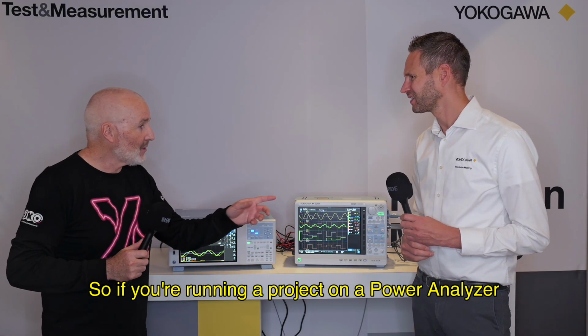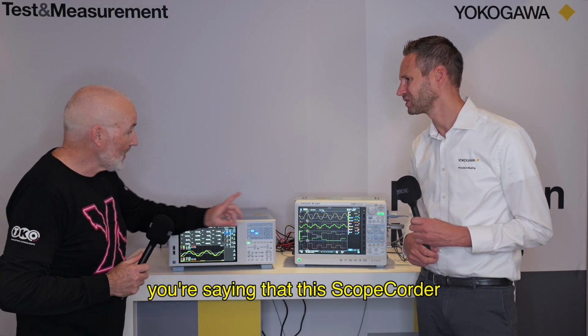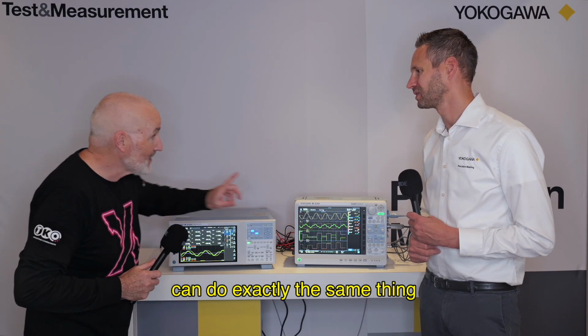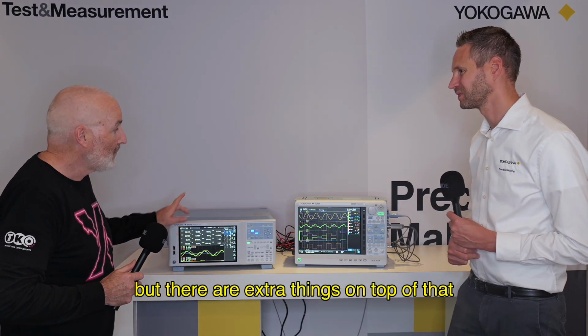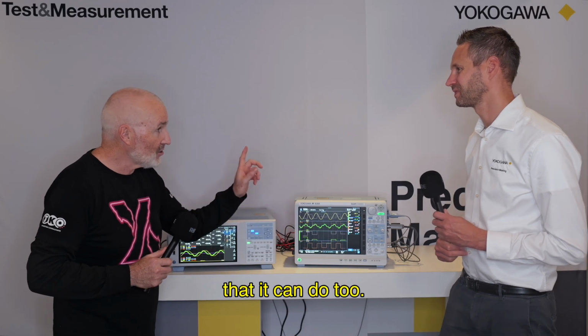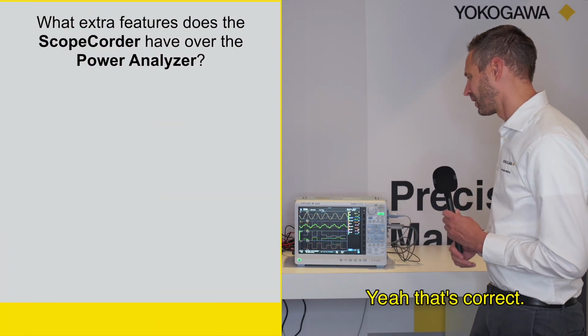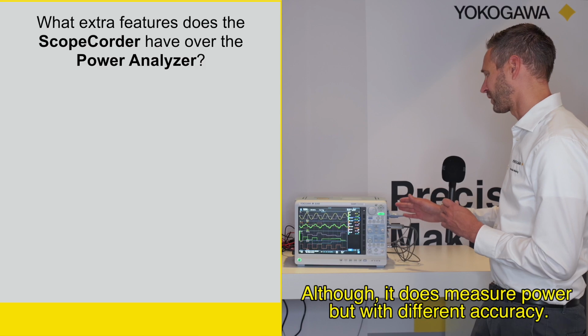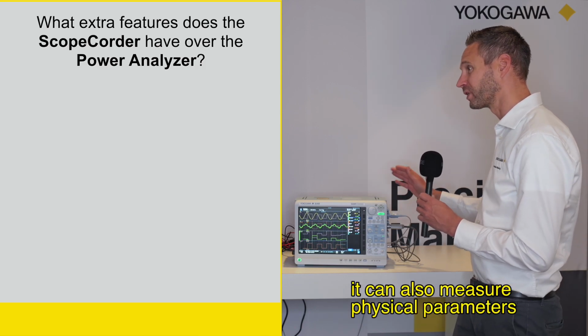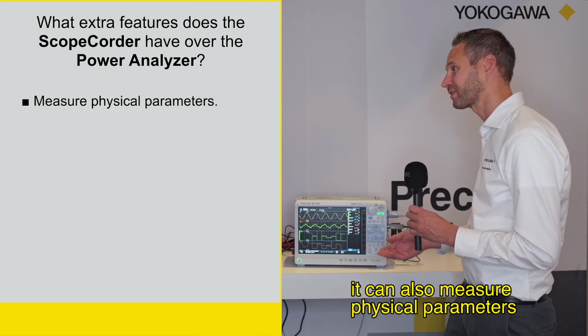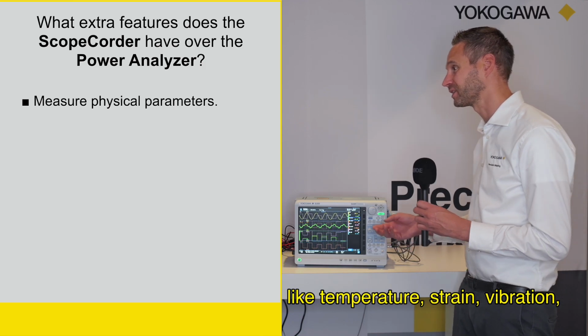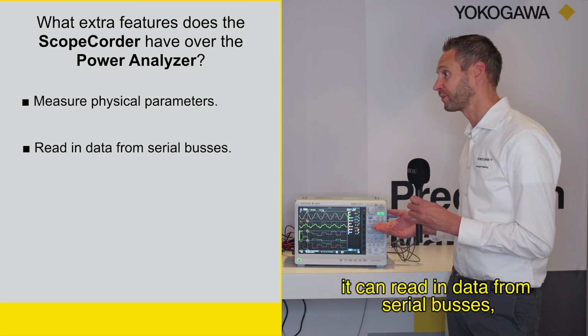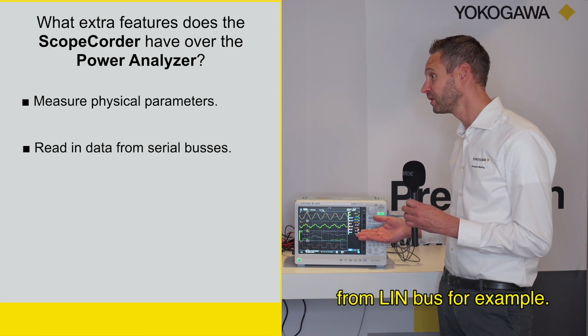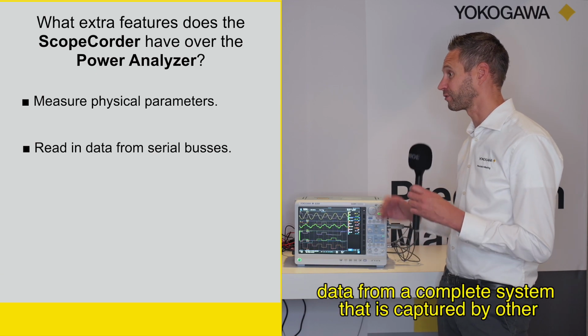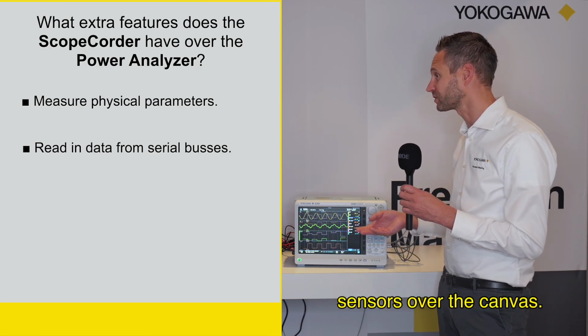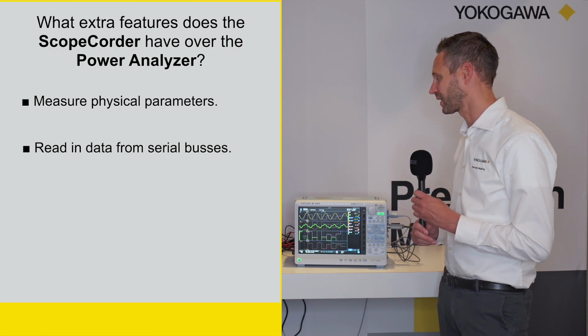So if you're running a project on a Power Analyser, you're saying that this ScopeCorder can do exactly the same thing this Power Analyser can do, but there are extra things on top of that that it can do too. Yeah, that's correct. Although it does measure power but with different accuracy, on top of doing this, it can also measure physical parameters like temperature, strain, vibration. It can read in data from serial buses, from CAN bus and LIN bus, for example. So you can also correlate data from a complete system that's captured by other sensors over the CAN bus. You can capture as well.